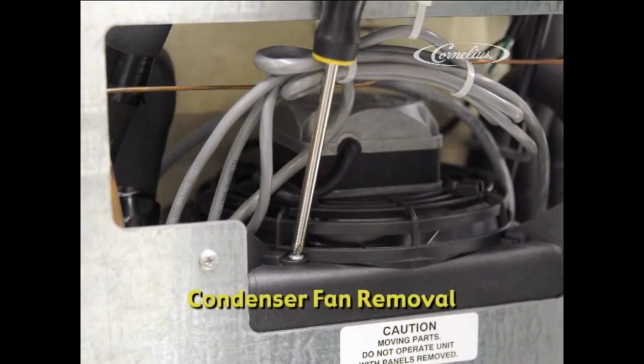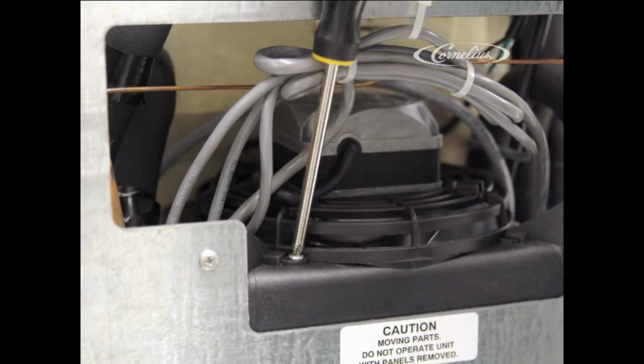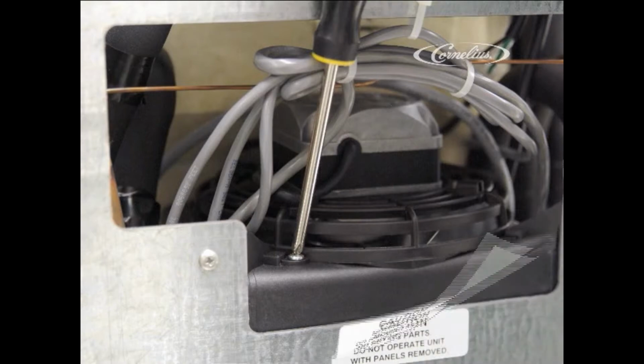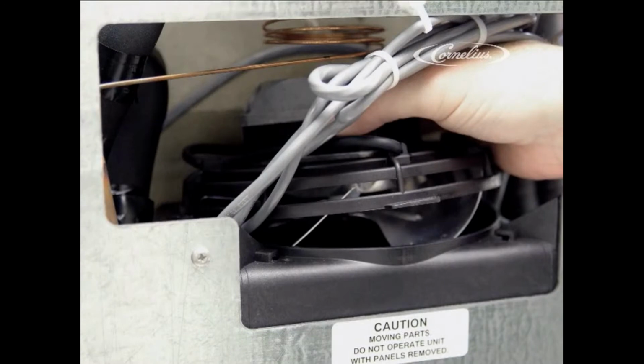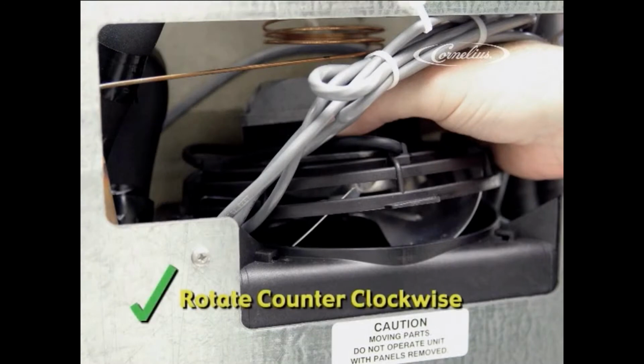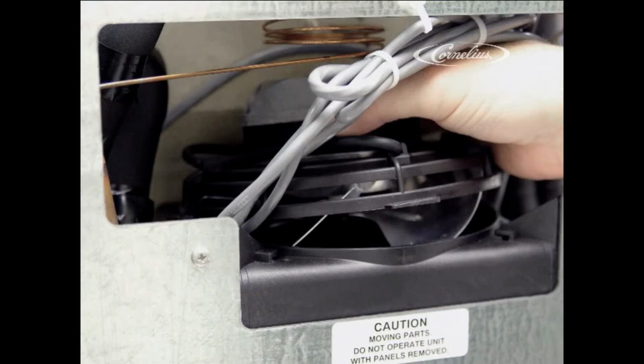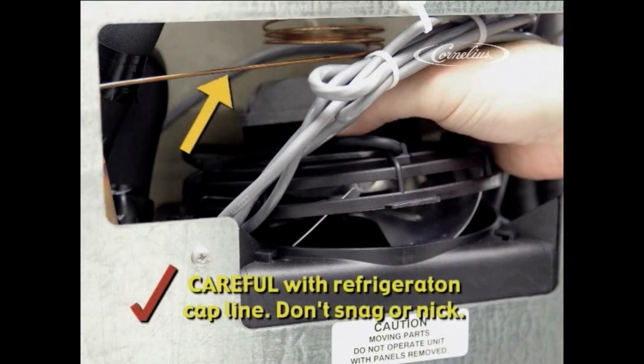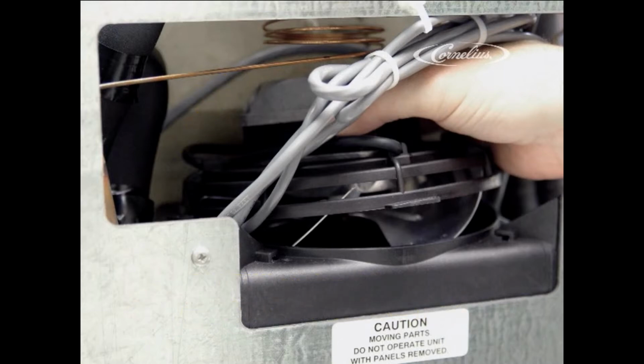As you know, good airflow through the condenser is critical to good refrigeration performance. To clean the condenser, we first need to remove the motor fan assembly. This is done by simply removing this screw and rotating the assembly counterclockwise until the tabs clear and the motor can be lifted out. Be careful when removing the fan assembly, as the refrigeration cap line runs across the back. Snagging or nicking this can cause a major refrigeration leak.